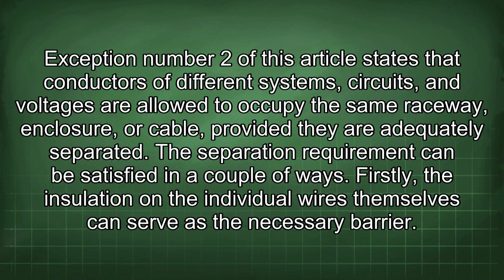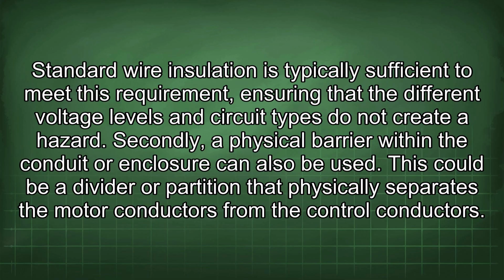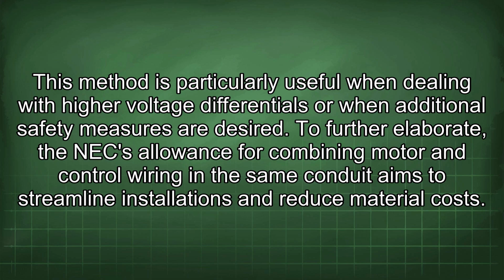The separation requirement can be satisfied in a couple of ways. Firstly, the insulation on the individual wires themselves can serve as the necessary barrier. Standard wire insulation is typically sufficient to meet this requirement, ensuring that the different voltage levels and circuit types do not create a hazard. Secondly, a physical barrier within the conduit or enclosure can also be used. This could be a divider or partition that physically separates the motor conductors from the control conductors. This method is particularly useful when dealing with higher voltage differentials or when additional safety measures are desired.